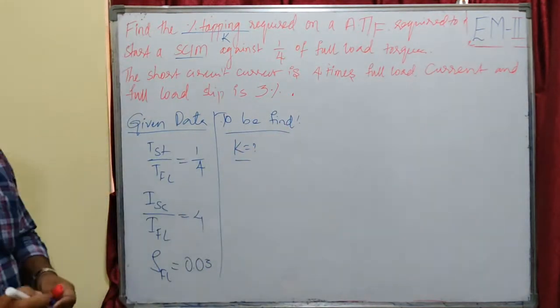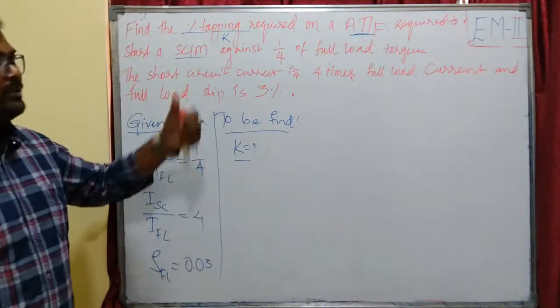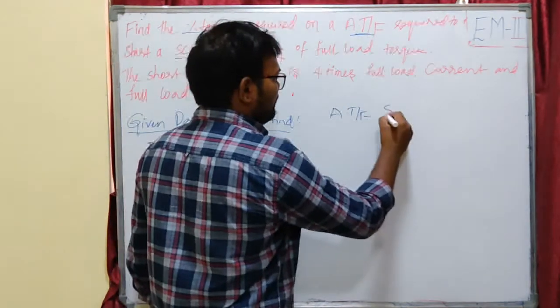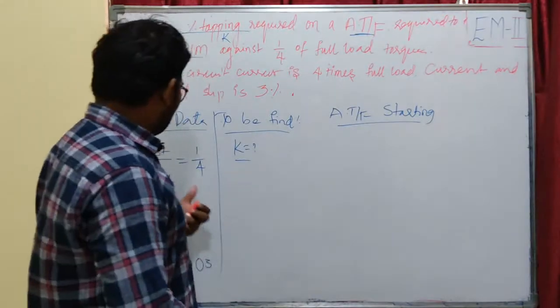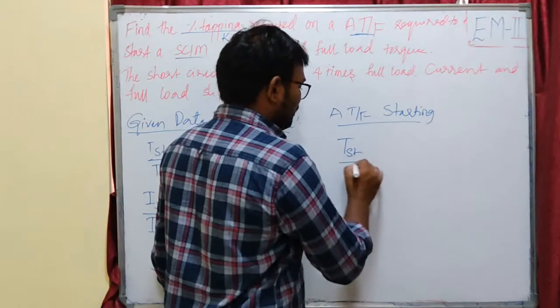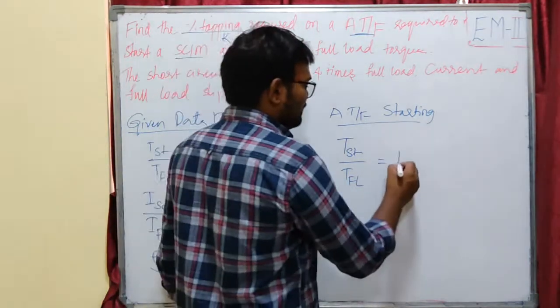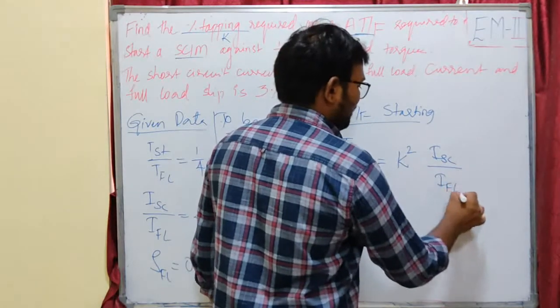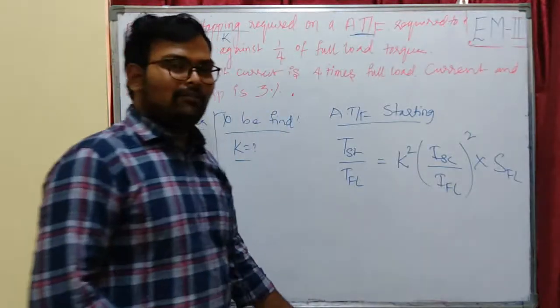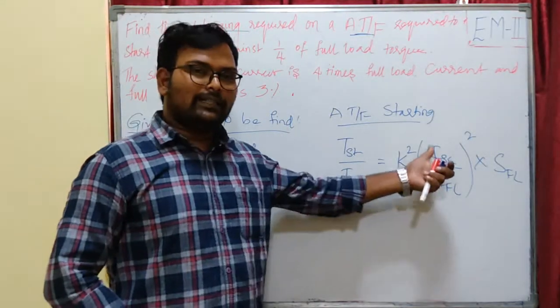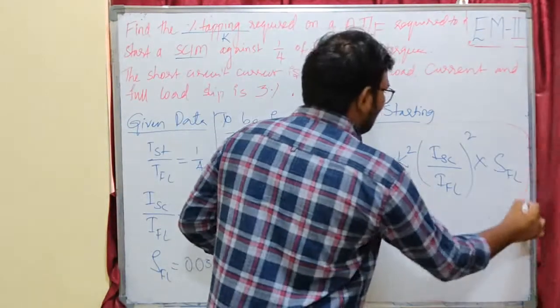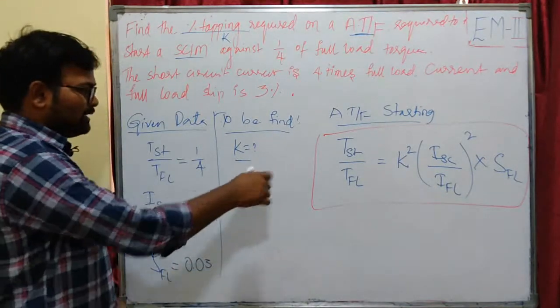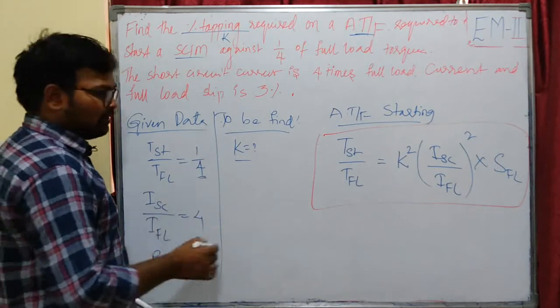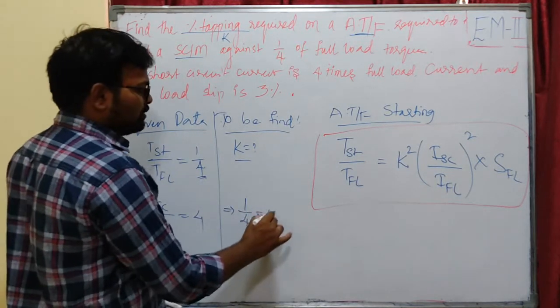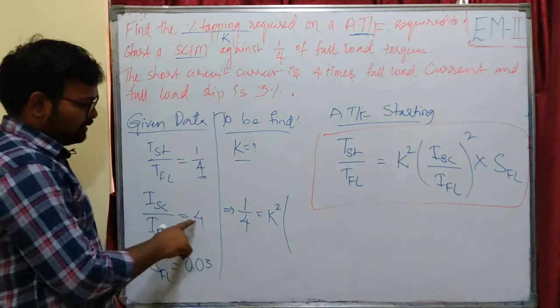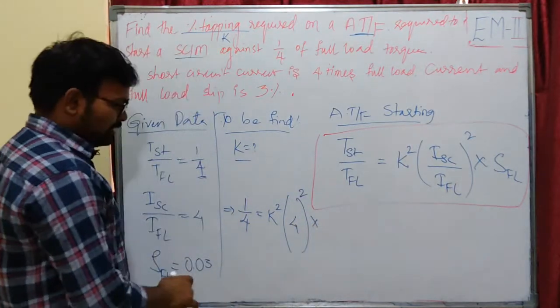K is how much? Because he has mentioned auto transformer and it is related to starting, we have the relation for auto transformer starting: the ratio of starting torque to full load torque TST by TFL equals K square times (ISC by IFL) whole square into SFL. So you can substitute the values to get the percentage tapping. What is to be found? K. TST by TFL is 1 by 4. So 1 by 4 equals K square, which is to be found, times the ratio between short circuit current and full load current, 4, whole square, into SFL, which is 0.03.